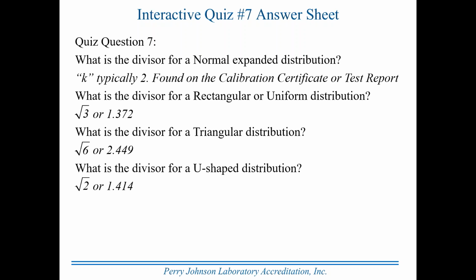Now, on the opposite hand, the triangular distribution is associated with laboratories where the temperature is center controlled. So as soon as it drops below 20, the heat comes on, and as soon as it gets above 20, the air comes on, and you have the heat and the air running practically all the time, and they're battling each other, trying to maintain that exact 20 degrees.